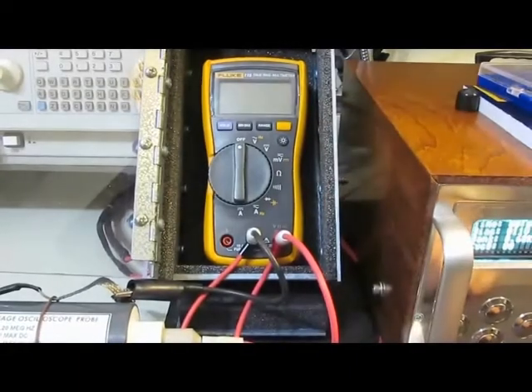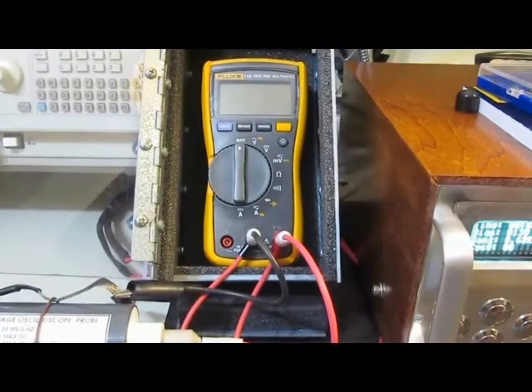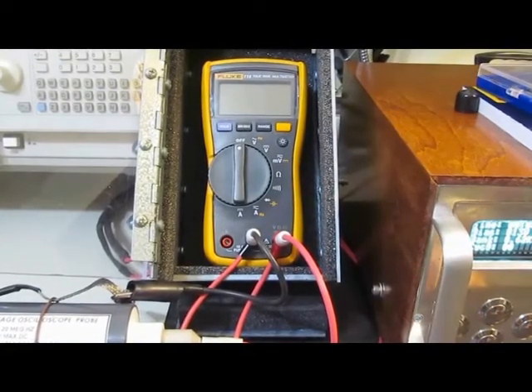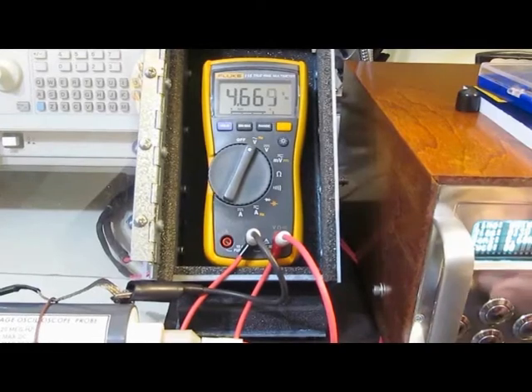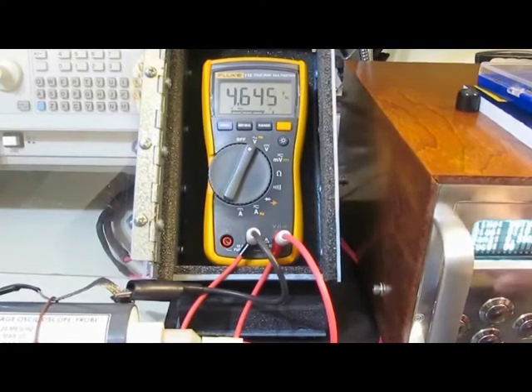We're going to start with 1 kV. This will be a 100 microsecond full width half-height, 2 ohm source impedance. And again, we'll run positive and negative transients with each mode of the meter, and then we'll perform a functional test. Let's go ahead and get started.